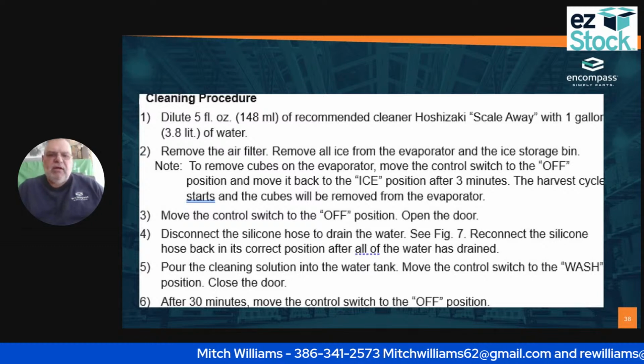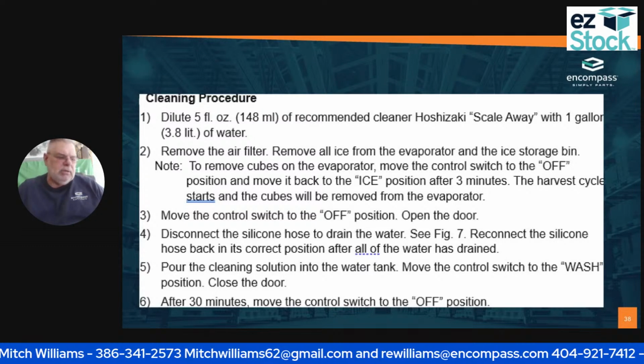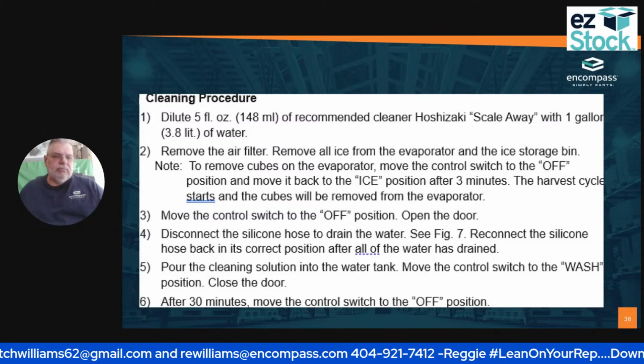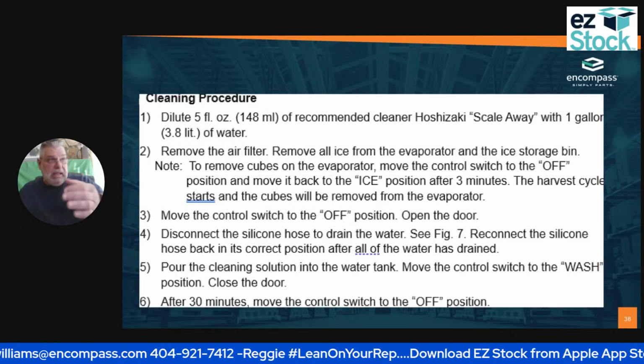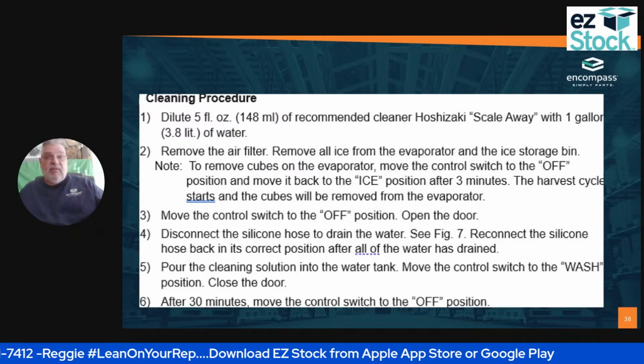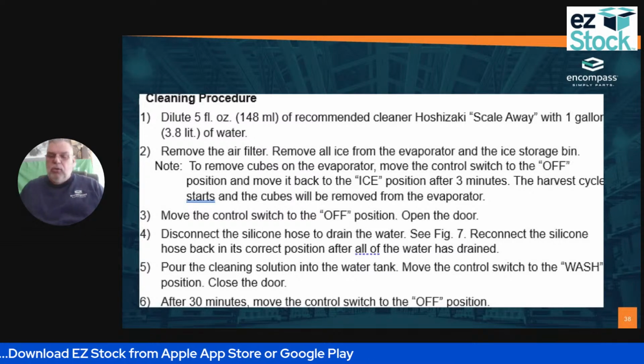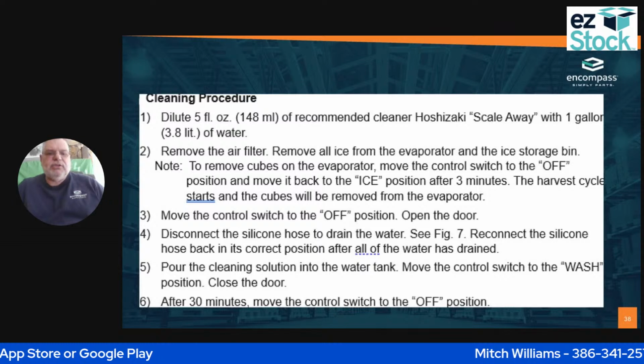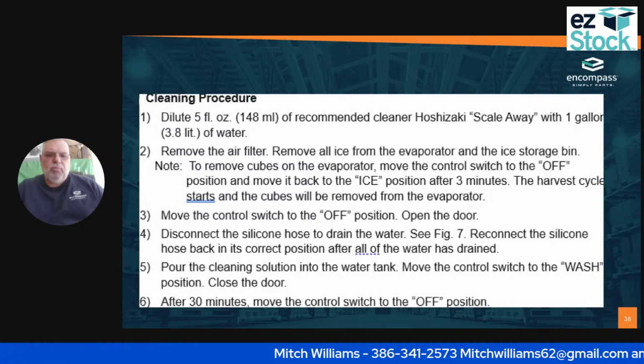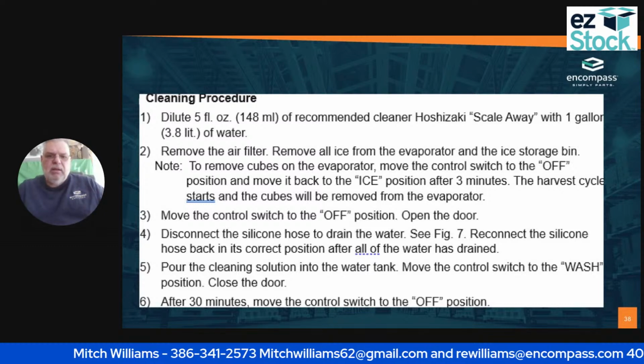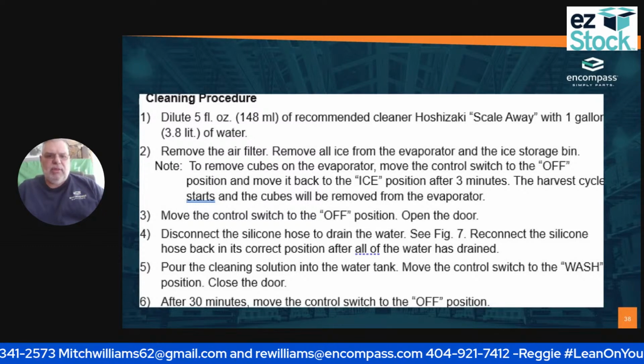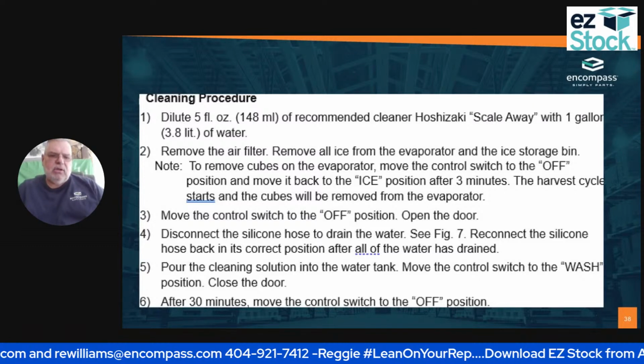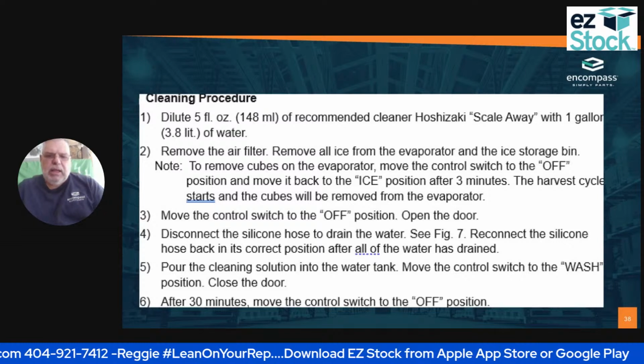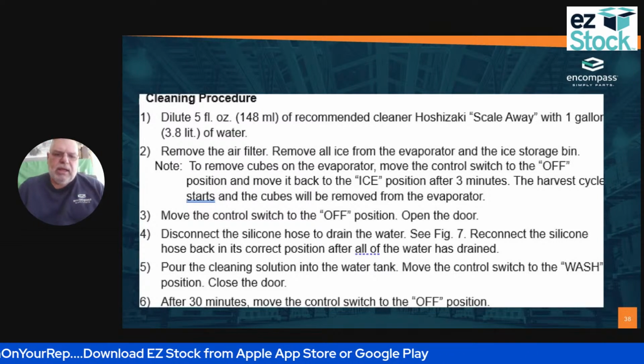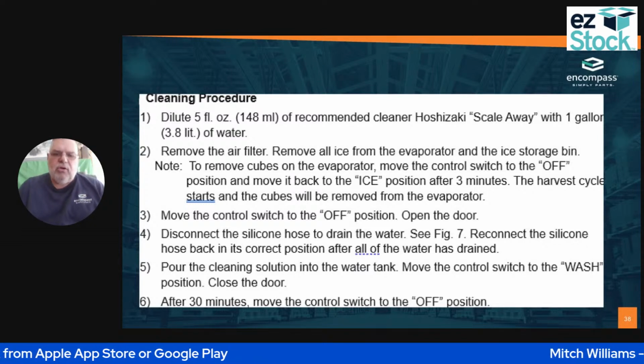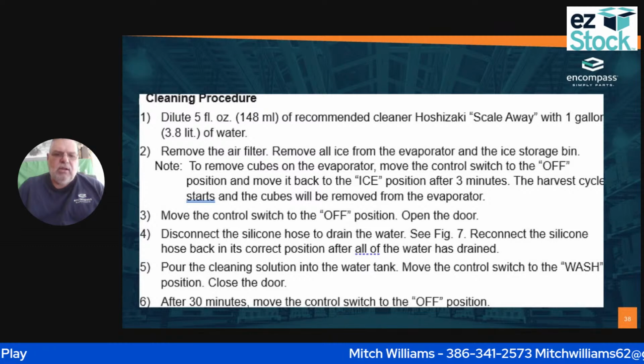Okay. Then I'm going to remove the air filter and remove the ice from the machine. You're not going to have any ice, or you shouldn't. But still, if I'm out here, I'm going to check and make sure that I have no ice, because if I have ice, I've got to throw it away or put it in a cooler or something. Okay. So I'm going to move the control switch to off, open the door, disconnect the silicone hose, the drain, and drain the water, which you saw in the previous slide. Then I'm going to reconnect the silicone hose back to the correct position, and once all the water is drained, pour that cleaning solution into the water tank, move the control switch to wash, and then close the door.